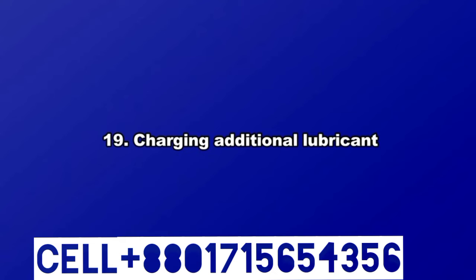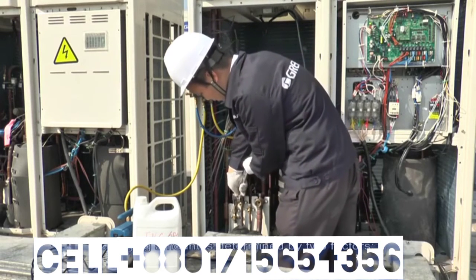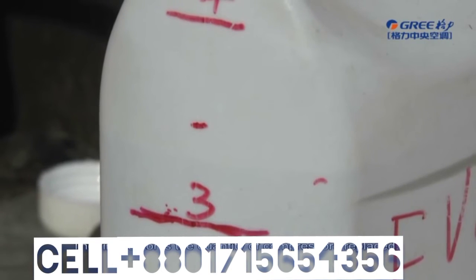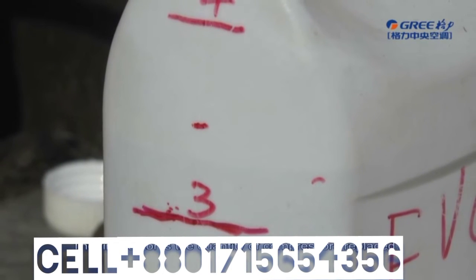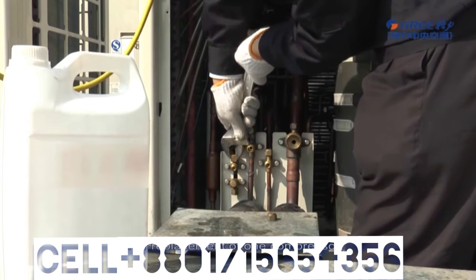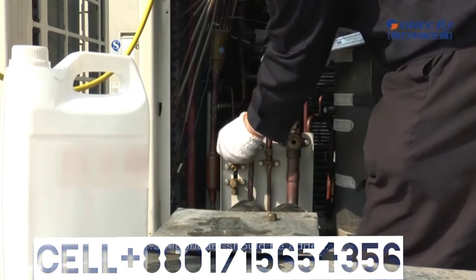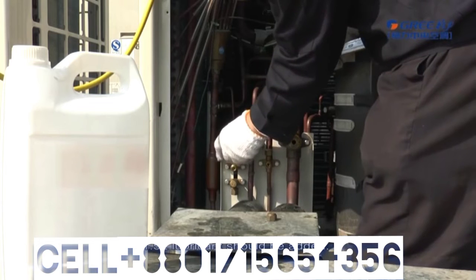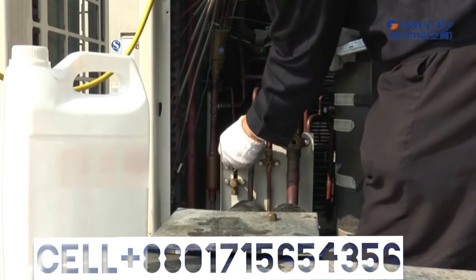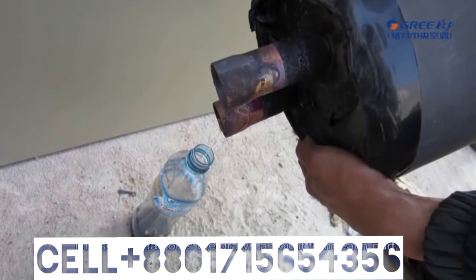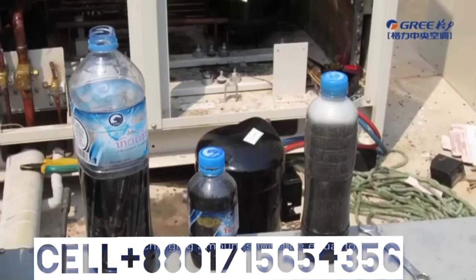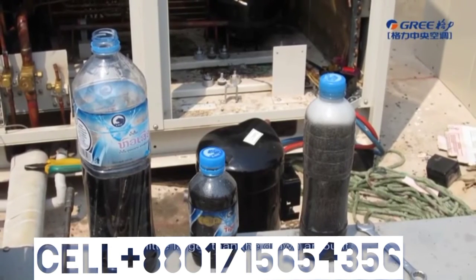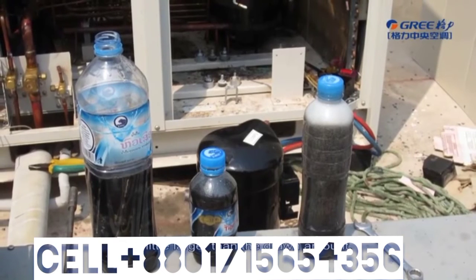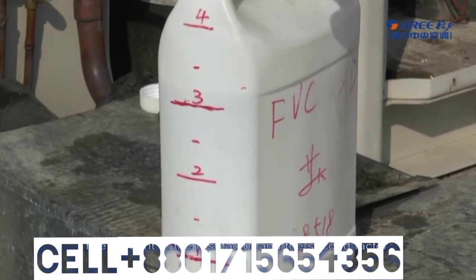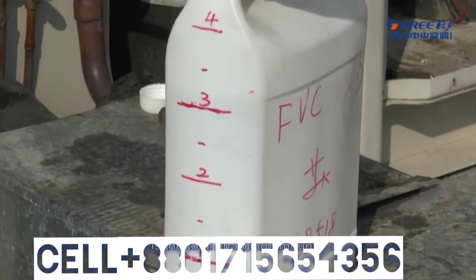(19) Charging additional lubricant. Charging amount is determined by two factors. The first factor is the quantity of compressors replaced. For replacement of one compressor, 1.5 liters lubricant should be added. The second factor is the joint amount from each part. The charging amount should be equal to or a little larger than the joint amount. The amount of the first factor and second factor is the total charging amount.